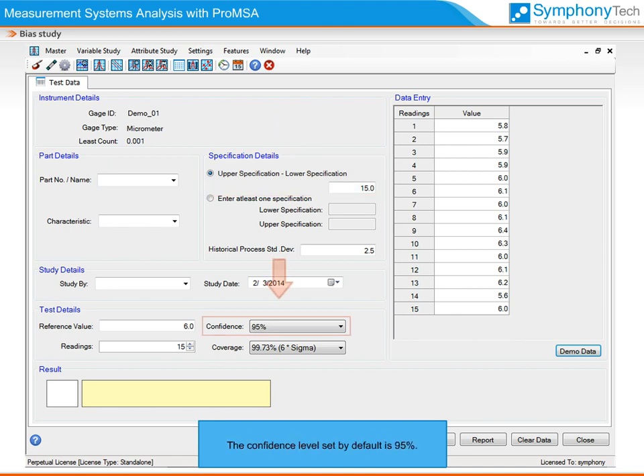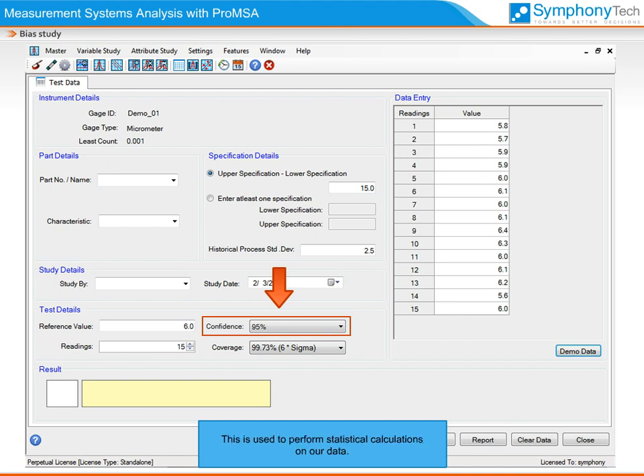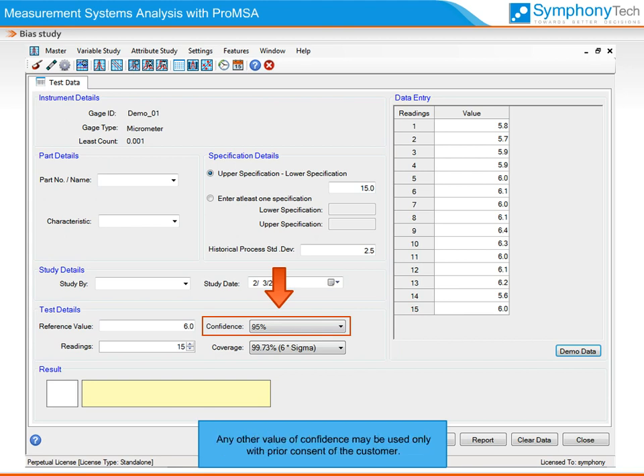The confidence level set by default is 95%. This is used to perform statistical calculations on our data. The AIAG MSA standard recommends that a 95% confidence level should be used for bias evaluation. Any other value of confidence may be used only with the prior consent of the customer.